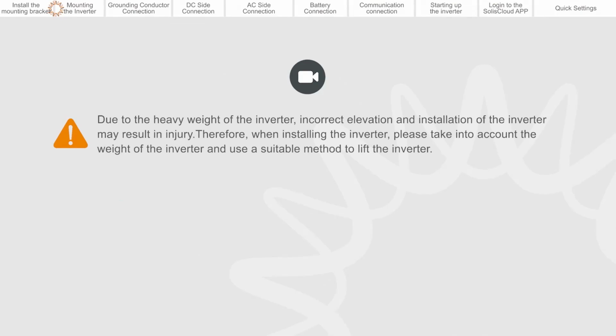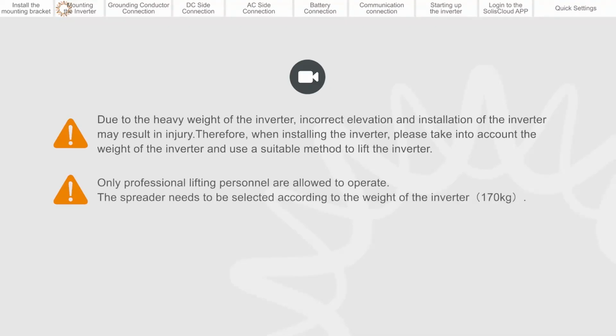Warning! Due to the heavy weight of the inverter, incorrect elevation and installation of the inverter may result in injury. Therefore, when installing the inverter, please take into account the weight of the inverter and use a suitable method to lift the inverter. Only professional lifting personnel are allowed to operate. The spreader needs to be selected according to the weight of the inverter, 170 kilograms.